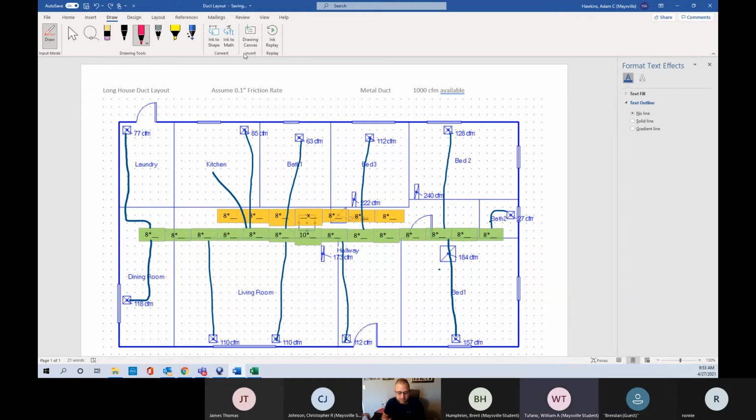Now, what if I wanted to move 120 CFM through that vent? Could I do it? Yeah. What's my static at that point? It is way down there, like 0.025. 0.0125. 0.01, yeah, about 0.01. So by reducing his static pressure, he reduces his velocity, which reduces his noise.